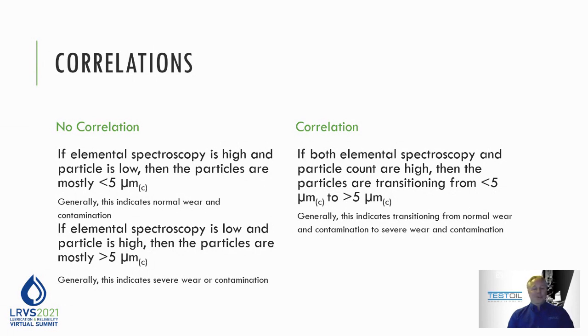And as I always jokingly say to people when they ask, how come there's two different tests for measuring the same thing? I say, because they don't see it the same way. And if they don't see it the same way, you're getting more information, right? And that's a common question that gets asked of other things like degradation or perhaps insolubles and varnish testing. People are always wondering, why are there more than one test to do this? It's because they're seeing it from a different perspective. And that different perspective sometimes will correlate with your results and sometimes won't correlate. But in both cases, you're generally still learning something about that particular parameter.